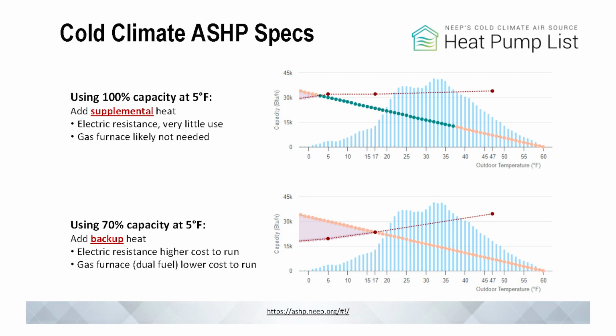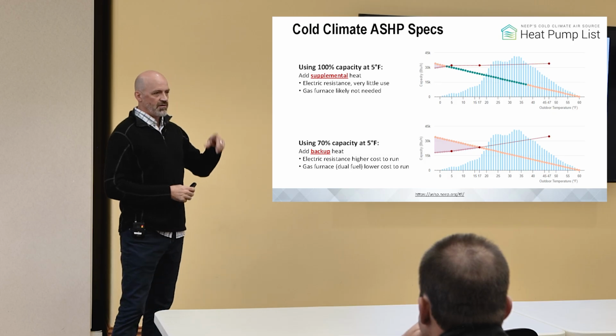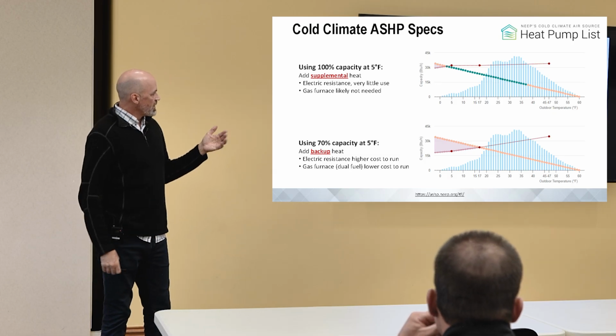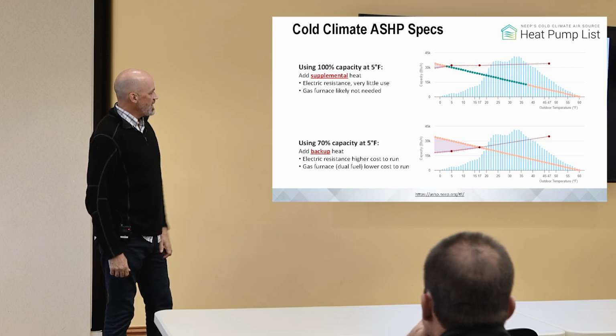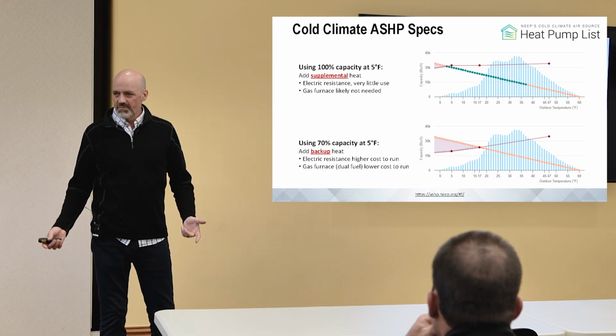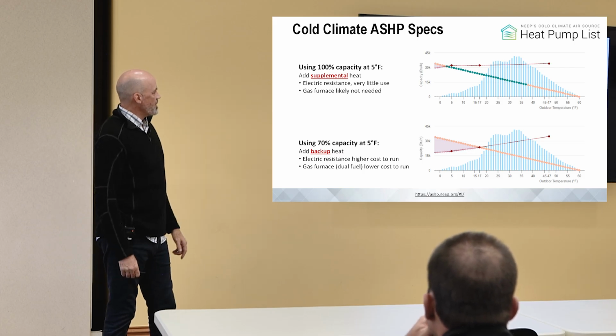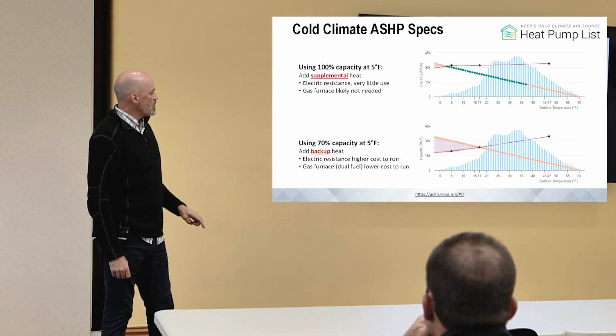The line sloping down to the right, high on the left, low on the right, is the heat load of the house. Is everybody comfortable with that concept? The colder it gets, the higher the heating load goes. We're not really worried about heating the house at 50 degrees, maybe a little, but not really—what we're really worried about is those cold temperatures.